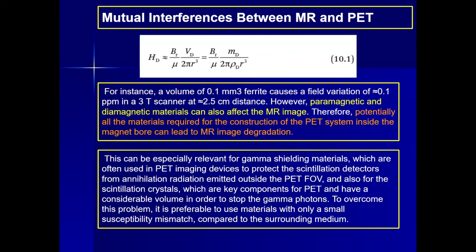For instance, a volume of 0.1 mm cubed of ferrite causes a field variation of approximately 0.1 ppm in a 3 Tesla scanner at 2.5 centimeter distance. However, paramagnetic and diamagnetic materials can also affect the MR images. Therefore, potentially all materials required for the construction of the PET systems inside the magnet bore can lead to MR image distortion and degradation. This can be especially relevant for gamma shielding materials, which are often used in PET imaging devices to protect the scintillation detectors from radiation emitted outside the PET FOV, and also for the scintillation crystals, which are a key component for PET and have a considerable volume in order to stop the gamma photons. To overcome this problem, it is preferable to use materials with only a small susceptibility mismatch compared to the surrounding medium.